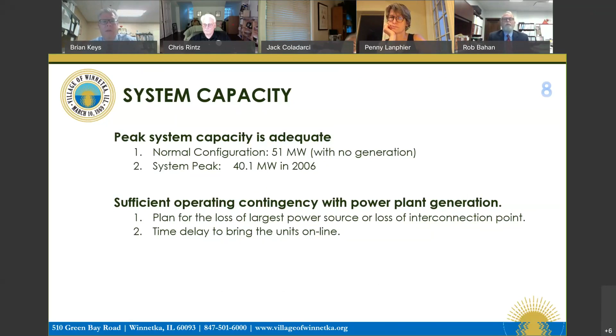Under a normal configuration with no generation, we're drawing power from the interconnects in our Northfield substation. The 30 plus the 21 means we can basically handle 51 megawatts, and our system peak was 40. So in the short term, or even mid-range, there really doesn't appear to be any capacity issues. We do have sufficient operating contingency with the power plant generation, but there is a time delay to bring it online.